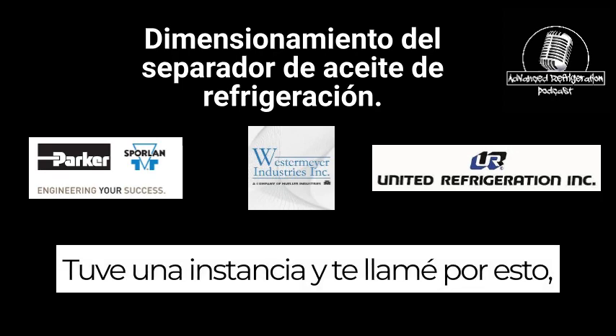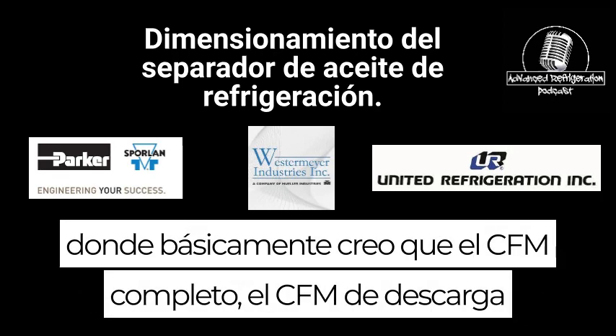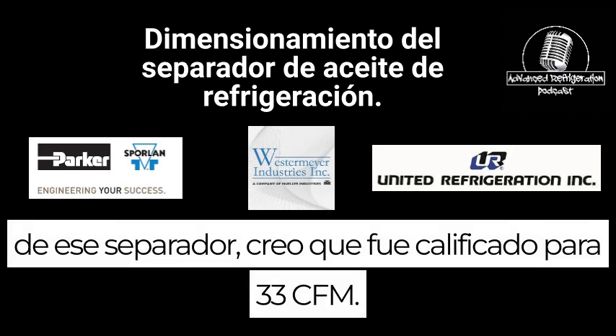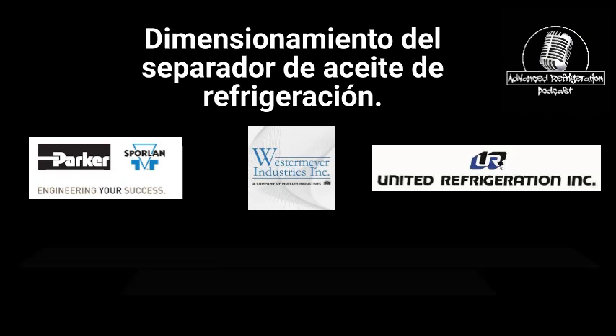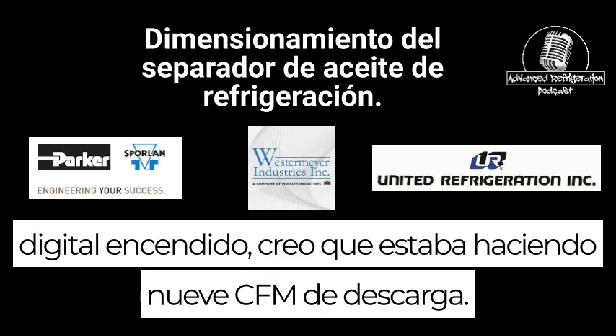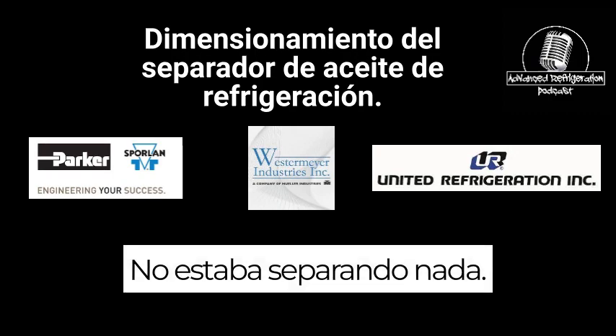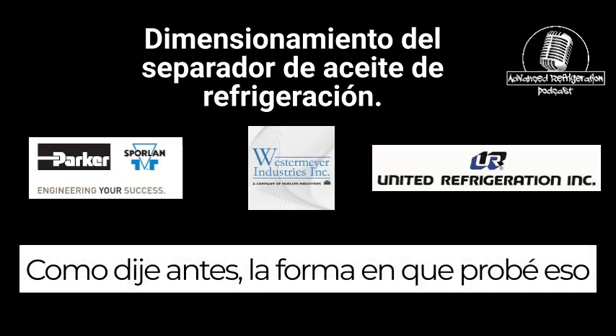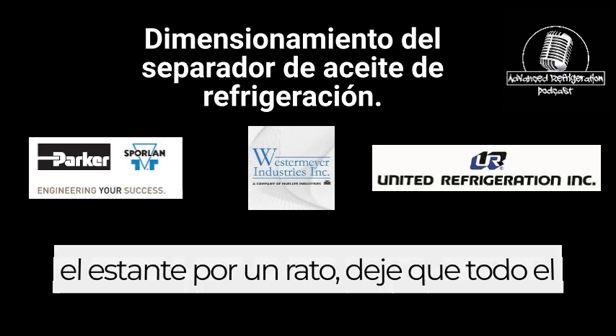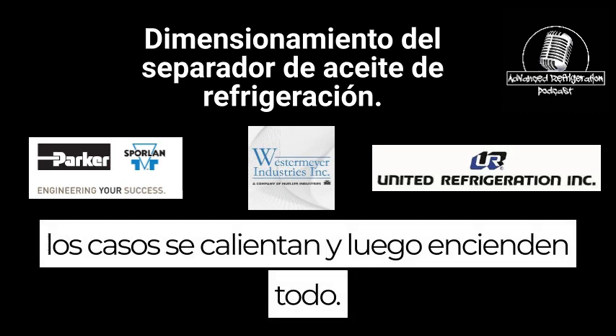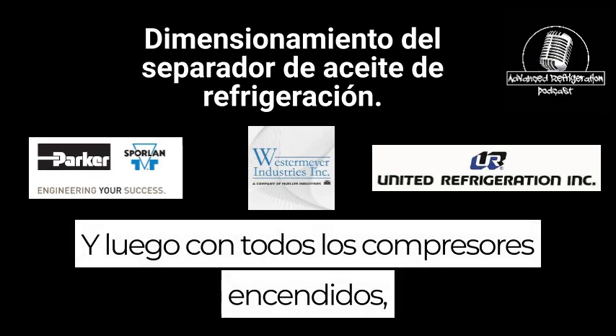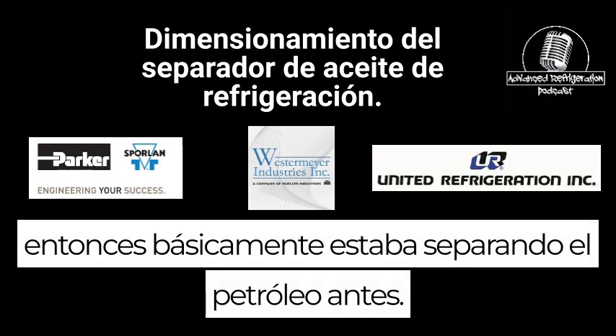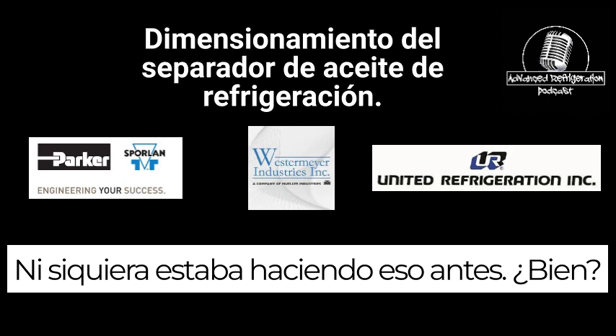I had an instance, and I called you about this, where the discharge CFM of that separator, I believe, was rated for 33 CFM. With one compressor on and one digital on, I think I was doing 9 discharge CFM. And it wasn't separating anything. The way I proved that was I shut off the rack, pumped down the rack for a little bit, let all the cases warm up, and then turned everything on. With all the compressors on, I was separating oil. Before, I wasn't even doing that. Right.